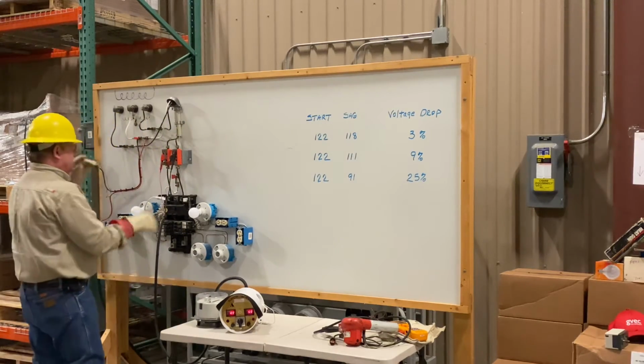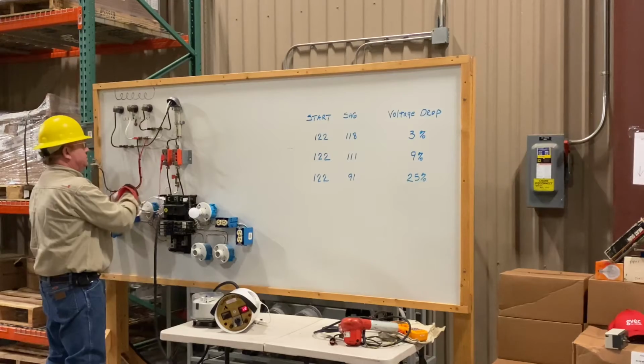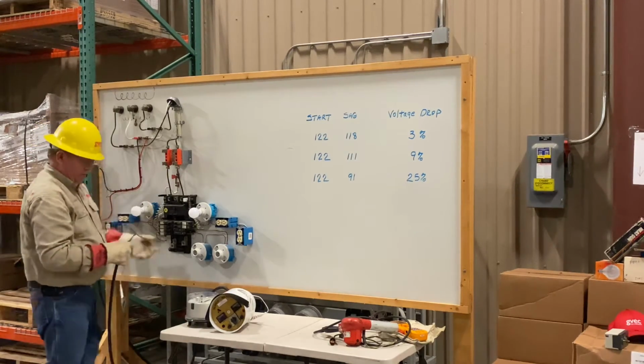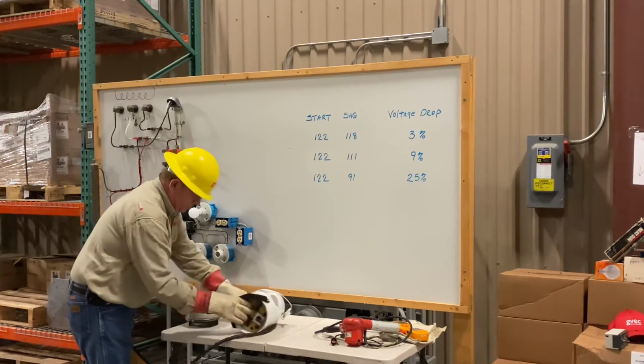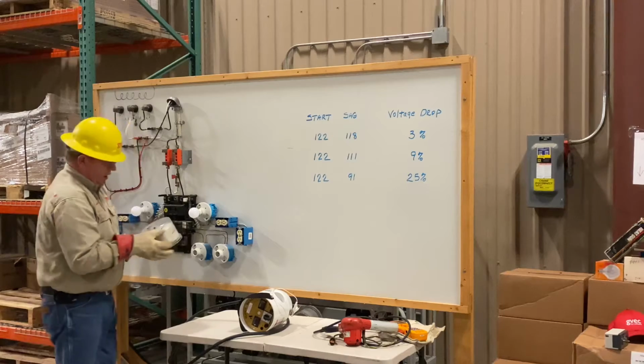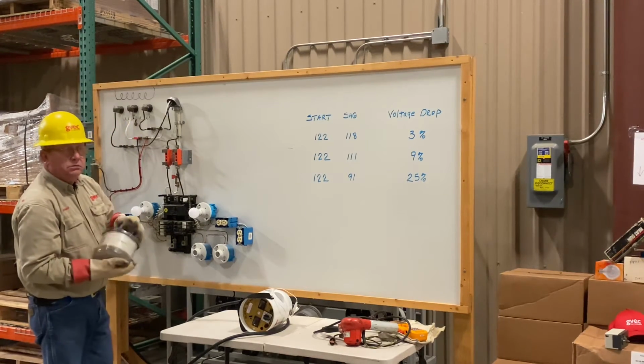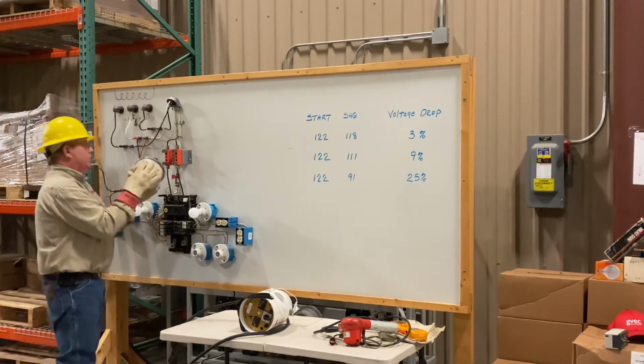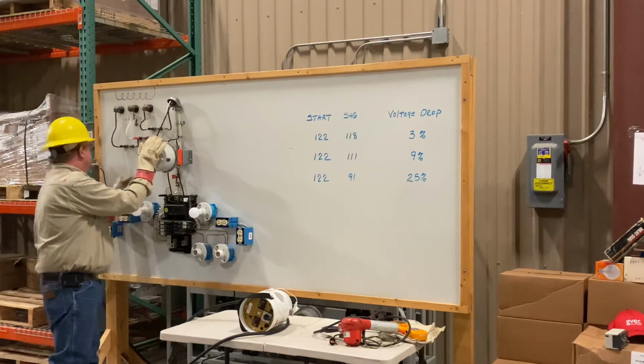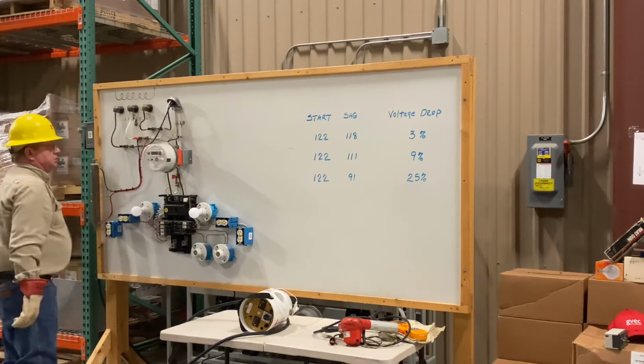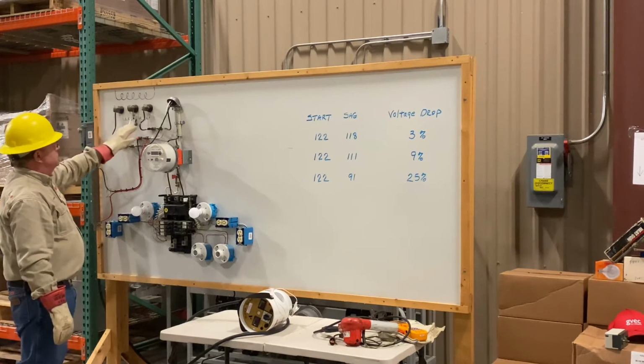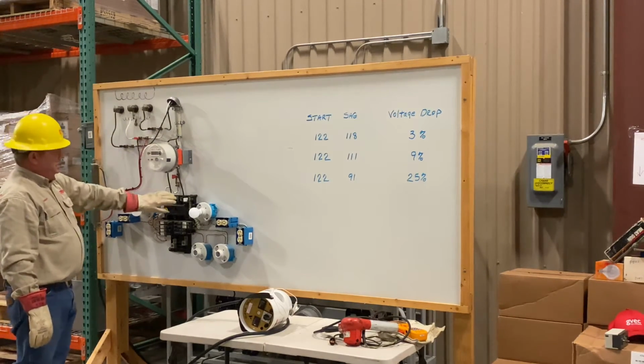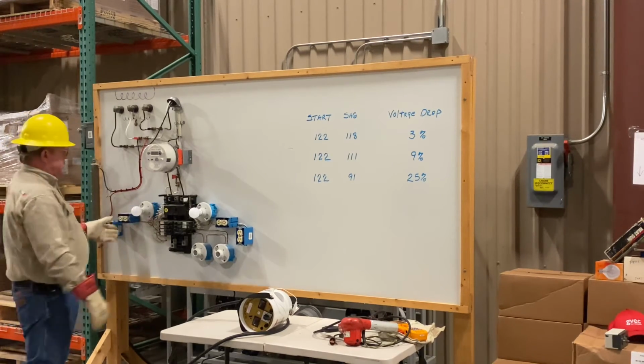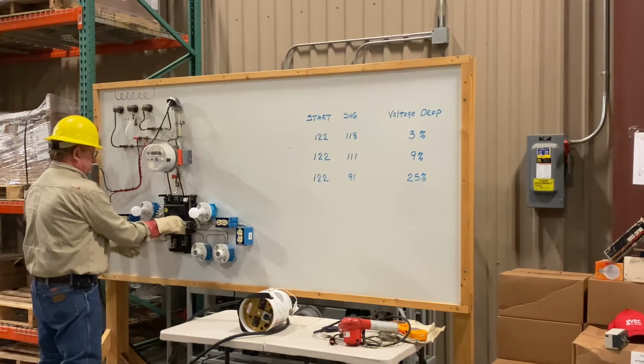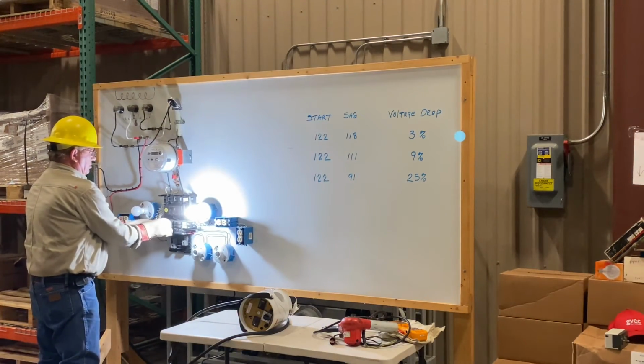Now we're going to disconnect this. Disconnect the hot legs. Disconnect the neutral. And we're going to stab the meter. As the co-op decides where our line stops, in a primary loop, we're responsible for the disconnect panel. That'll be up to your superintendents. So now we have transformer, service, riser through the meter into the disconnect panel. Disconnect panel's got load. So we know that the panel's hot.